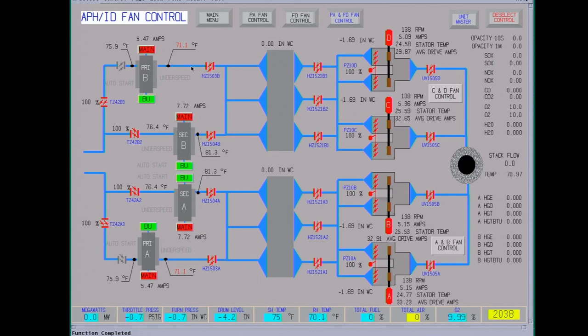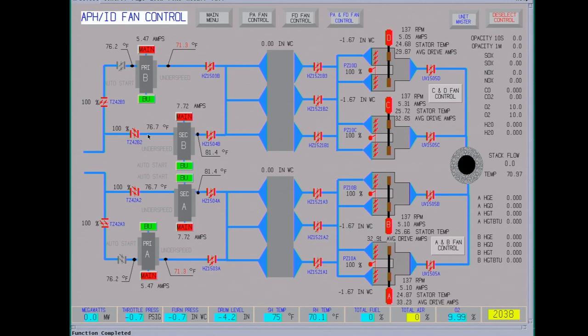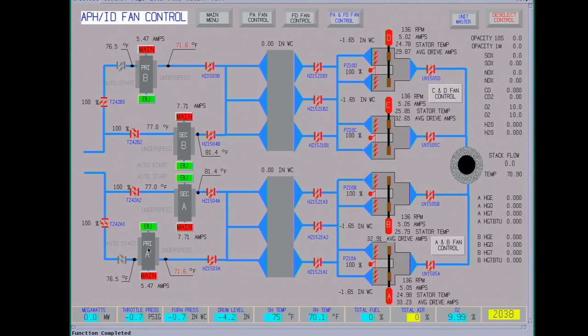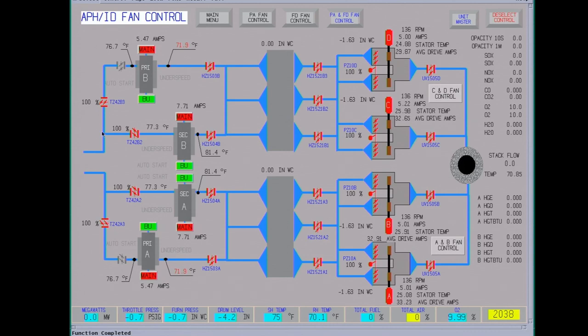Now this is just the gas stream coming from the boiler. These dampers we can move to regulate the temperature. Once we start up, we'll shut down the air to the primary air heater and put it on the side the pulverizers are running. These two are primary air preheaters. These are from the primary air fans. From here the air is going to the pulverizers. These are the secondaries, they come from the secondary air fan. They feed the boiler wind box, which runs your burner sleeve dampers and your over fire air for NOx control.